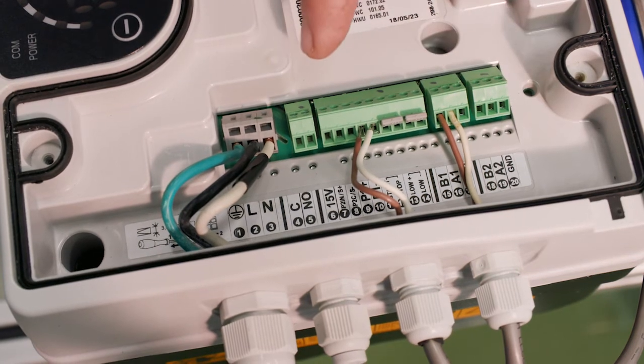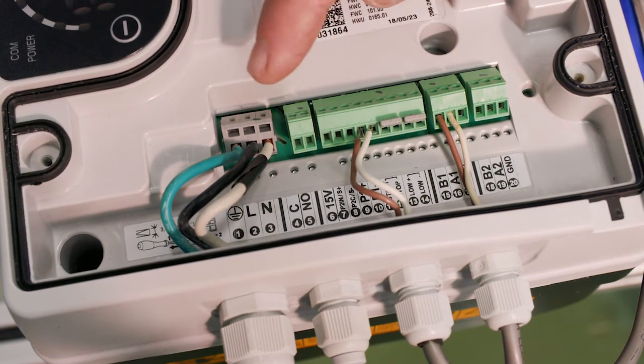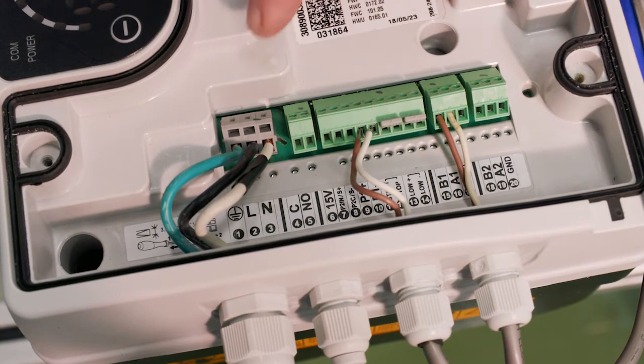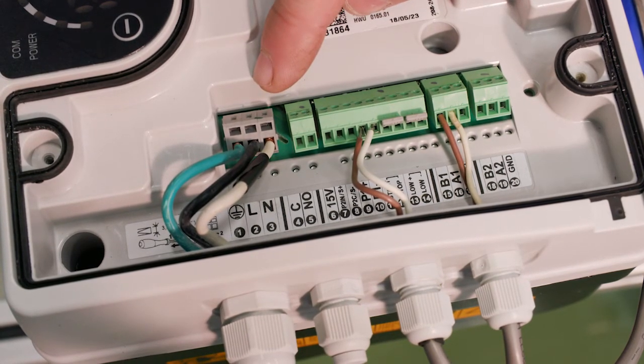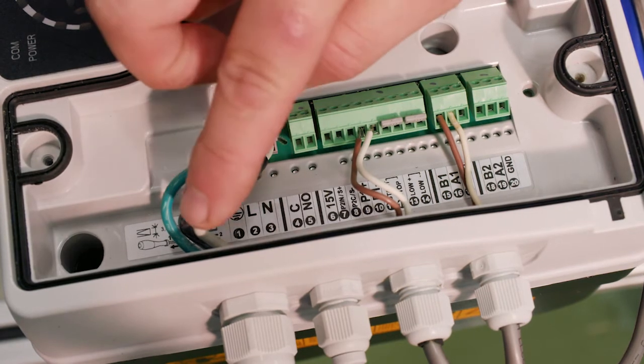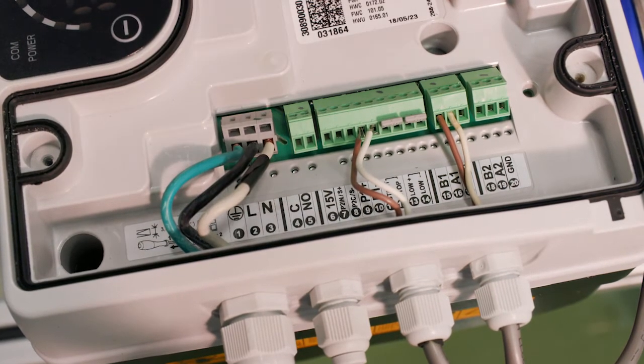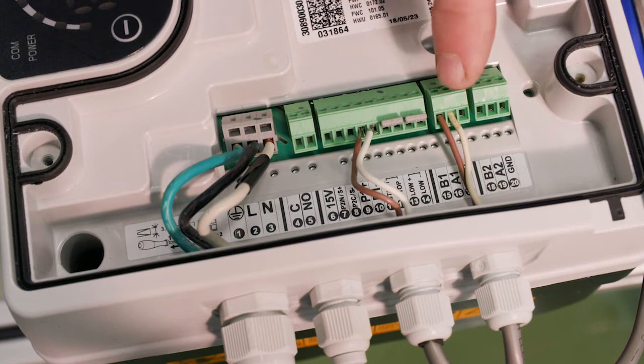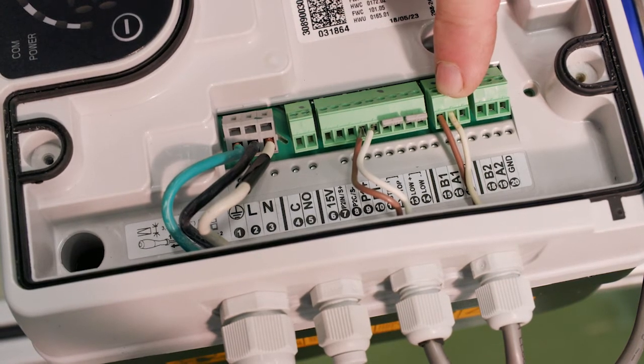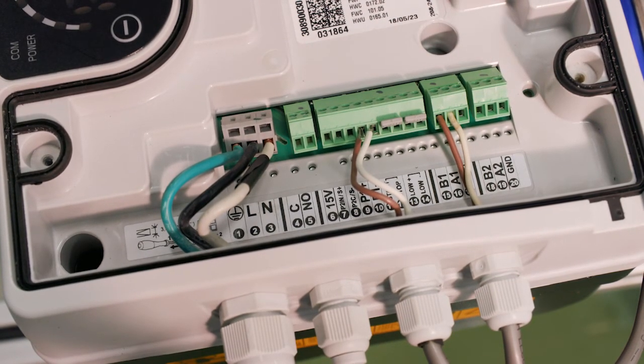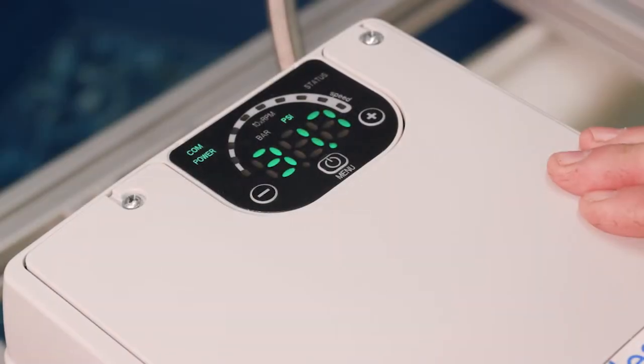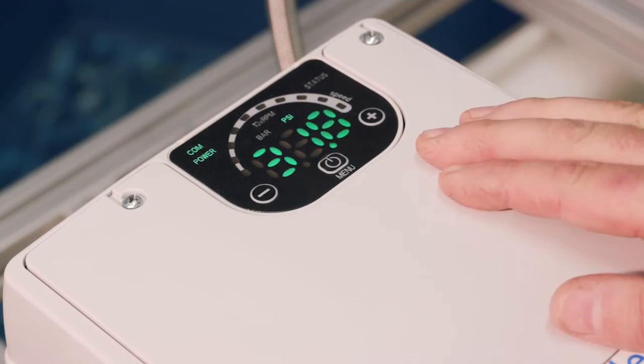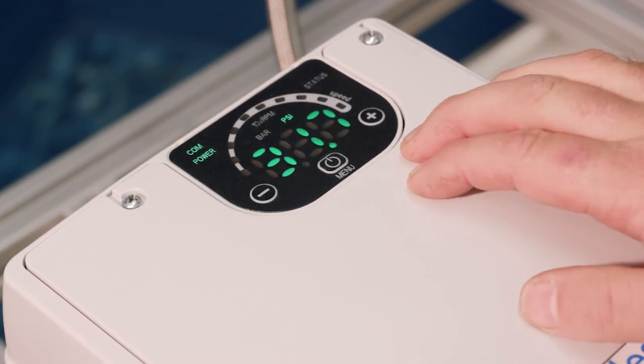So that's it in terms of the wiring. Simply input power. Just remember that this is a 230, 240 volt motor, so it has to have 2 hots, plus the transducer, and communication between the 2 drives. And that's it for the wiring. We've just finished the wiring for both units, exact same wiring for both, and we've put the cover on both of the units. So the next step would be to set up your keypad.